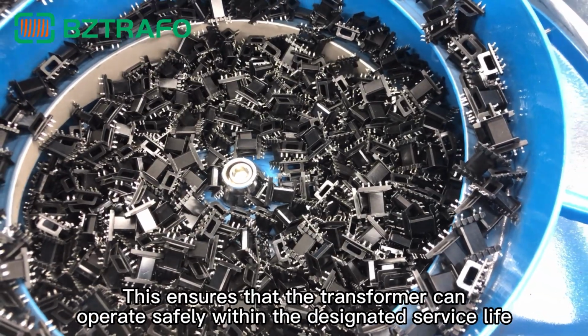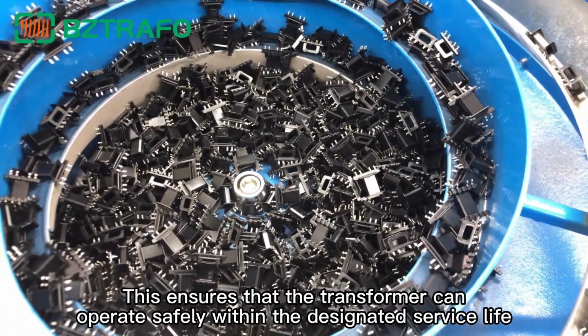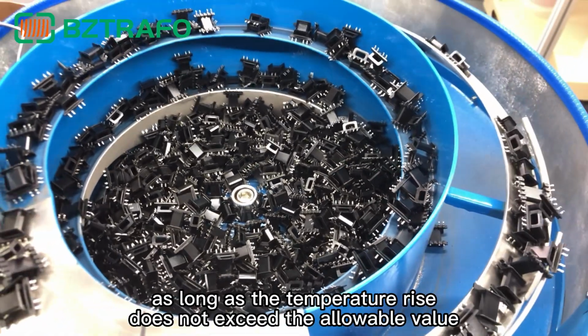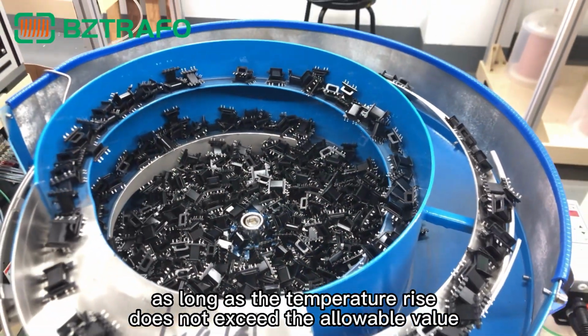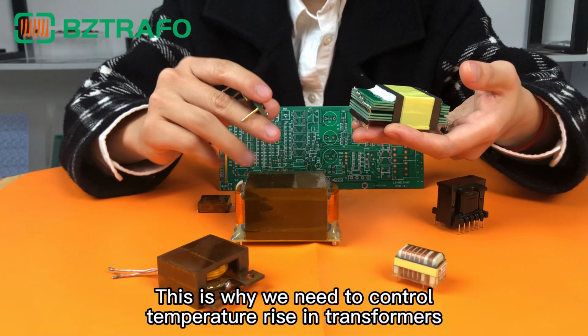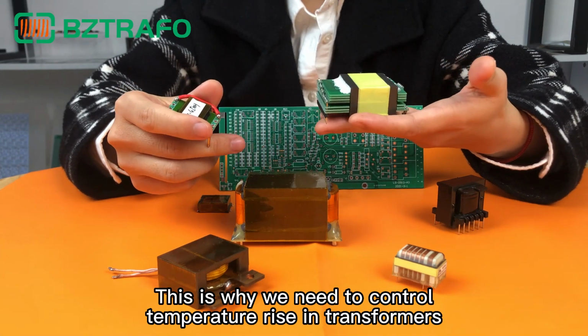This ensures that the transformer can operate safely within the designated service life, as long as the temperature rise does not exceed the allowable value. This is why we need to control temperature rise in transformers.